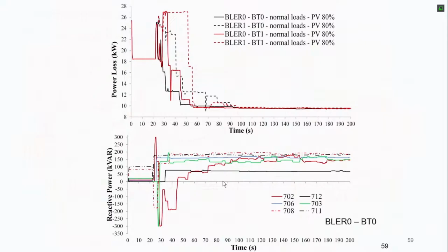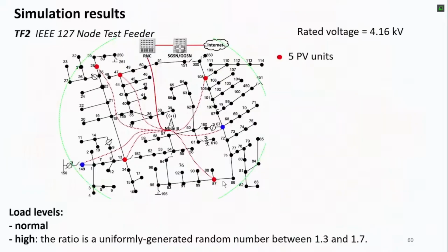If there are problems, delays in the communication and also some packet that is lost, I mean some cycle does not complete, so we have not only one transformer tap change, but also the transformer acts also in other points. But much less than without this secondary voltage. This is the reactive power injection or changes in the controller. So you see that it's stable after a little bit, one minute to two minutes, so it completes the cycle.